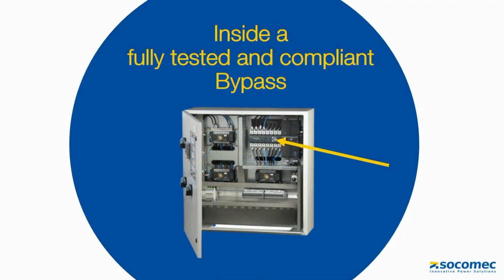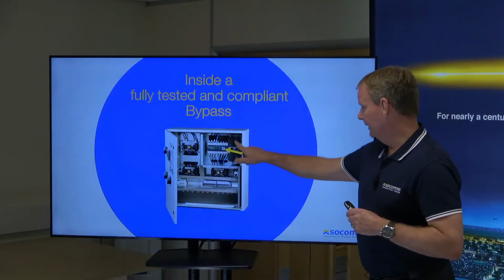This is what the inside of a fully tested and compliant bypass looks like. You can see the arrow, and there's a one piece, amongst all the other equipment, a one piece fully integrated controller ATS compliant to the product standard and also complies to BS 8519. So you can see it in here, okay?